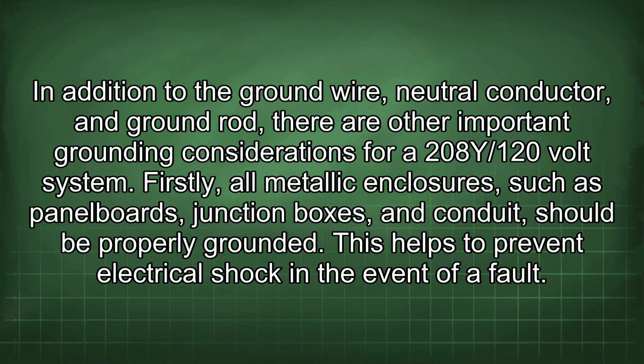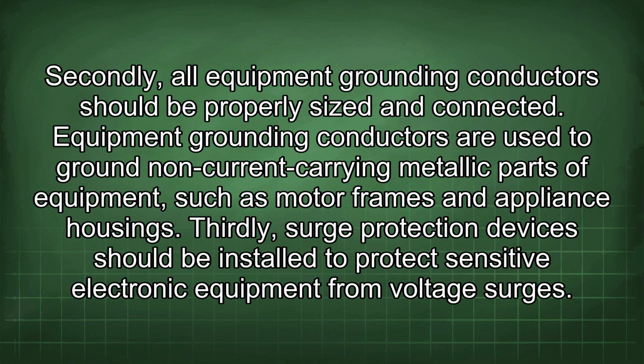In addition to the ground wire, neutral conductor, and ground rod, there are other important grounding considerations for a 208Y/120 volt system. Firstly, all metallic enclosures such as panel boards, junction boxes, and conduit should be properly grounded. This helps to prevent electrical shock in the event of a fault. Secondly, all equipment grounding conductors should be properly sized and connected. Equipment grounding conductors are used to ground non-current carrying metallic parts of equipment, such as motor frames and appliance housings.